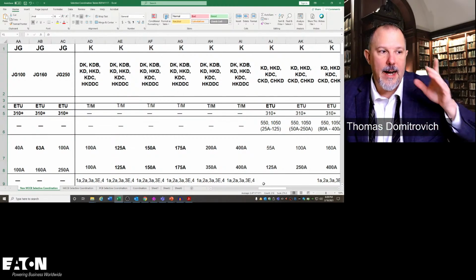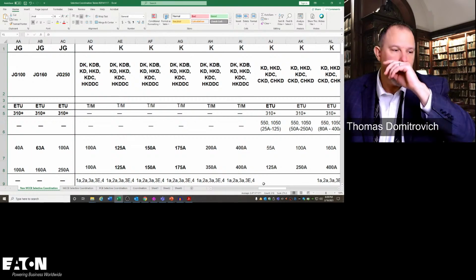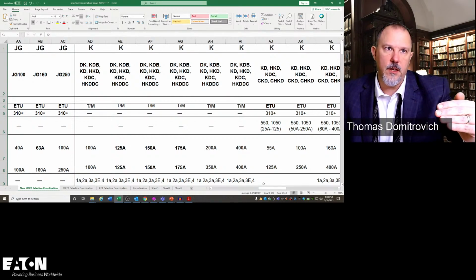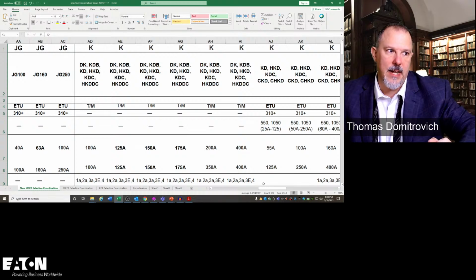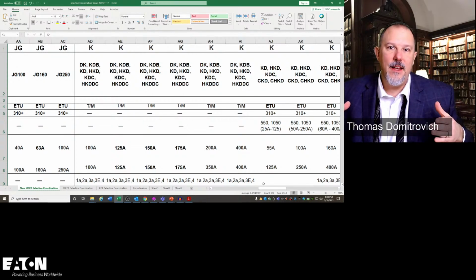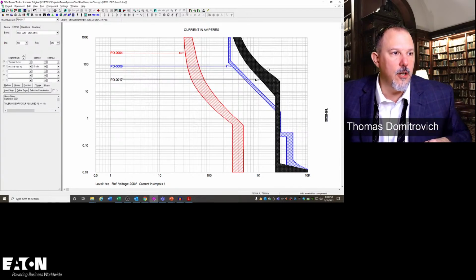But I've got a larger circuit breaker. You can make an argument to say, well, you increased the size of the conductor. The impedance of the conductor went down. The fault current went up. But your arcing currents are not going to be in the instantaneous. And look at this thermomag breaker.